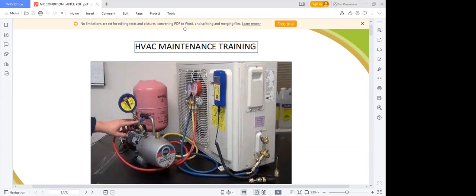If the cooling is too effective, and they require hot air to pass through the cooling, there's going to be heat exchange. The air coming from your room is at 20 and it's passing through the evaporator coil that is at 15. There will be heat exchange, and as the hot air goes through the evaporator, the temperature drops. If there is a blockage in the system, the evaporator coil will start blocking the cool air. Instead of it being exchanged, the cool air will keep reducing the temperature until water starts turning to ice on the surface.